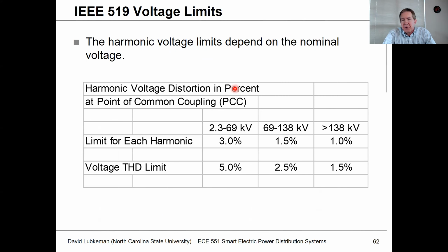As far as the voltages, what we're looking at, and this is also a function of the voltage, but for distribution level, the limit for each harmonic would be 3% with a total harmonic distortion limit of 5%. And so it depends on the voltage we're at, and this is typically the range we're interested in for distribution circuits. And so as a distribution system planner, what you're always on the lookout for is, do you have some industrial customers that could potentially cause these voltages to go up over these particular limits? And if these customers do cause issues, then they need to do some kind of mitigation strategy.